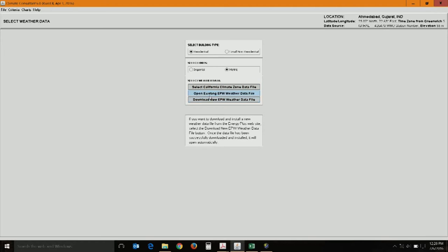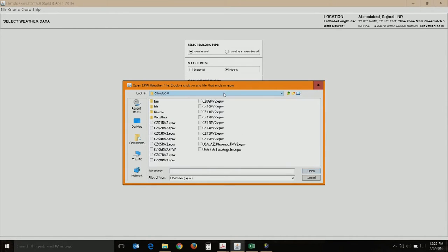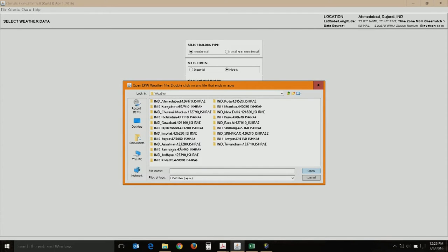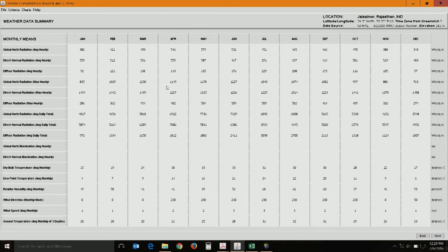The software asks whether you have climate data already or want to download weather data. The EPW format is Energy Plus Weather data. Weather files for around 35 Indian locations are available free online from ISHRAE — the Indian Society for Heating, Refrigeration and Air Conditioning Engineers — from whose site you can download and store files on your C drive. I have already downloaded data and will choose Jaisalmer, a hot and dry region. Once you choose a climate location, you get a climate summary on screen.